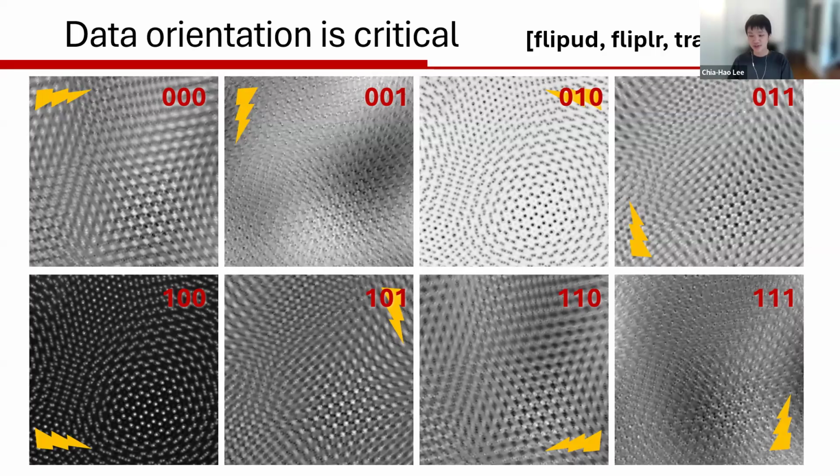At UIUC, we have two MPADs. They are installed with a 90-degree rotation. So similar things could happen to you as well. I believe most people with their MPAD detector, not even MPAD, with their 4D-STEM detector, might have a weird orientation flipping between the readout data and the GUI that they saw when they acquired the data set.